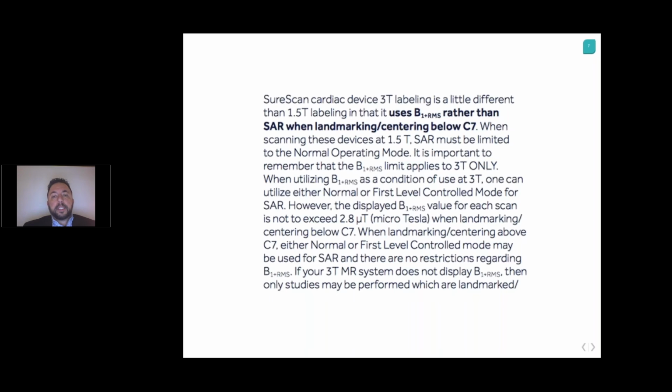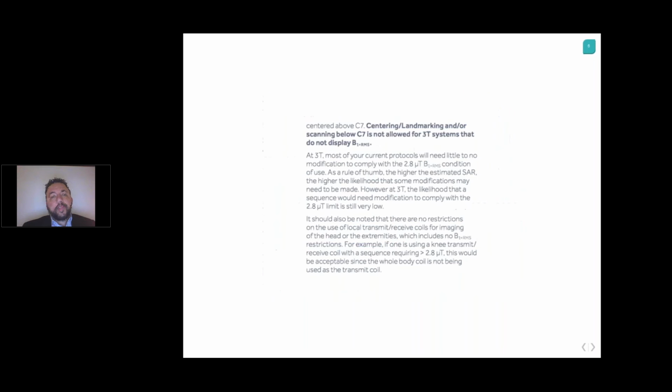So again, these conditions for use, newer systems, I believe Philips uses 2016 or beyond, that B1+RMS will be displayed coinciding with our SAR levels.